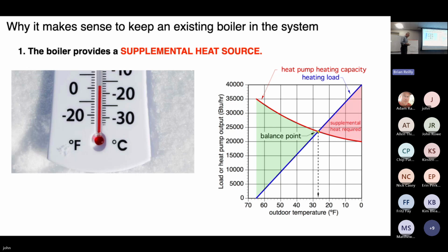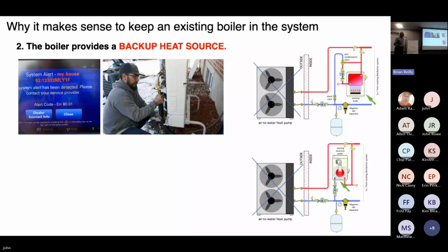You might say, well, should I oversize the heat pump? You can get away with oversizing an air to water heat pump. It's not the same as air to air because you have thermal mass in the system, especially with a buffer tank. We can put a 4-ton heat pump in a 3-ton building. That simulation I showed you for Plattsburgh, that was a nominal. Again, I use the word nominal because heat pump performance is a constantly changing number based on outside temperature as well as water temperature, right? But we can put a 4-ton heat pump into a 3-ton building. And basically it's going to shift the balance point towards a lower outdoor temperature. If we put a bigger heat pump in, this red curve would shift up like this, and it would shift towards that lower outside temperature. Okay. The boiler provides backup.